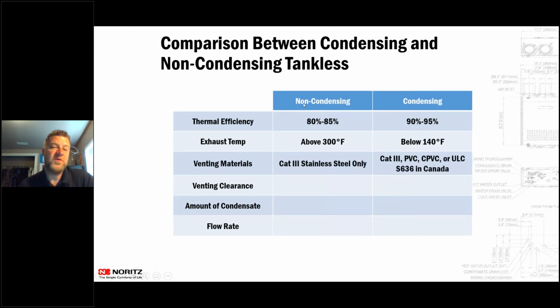So venting materials with non-condensing units, you had to use Cat 3 stainless steel, either 3, 4, or 5-inch stainless steel. With condensing units, you could still use that stainless steel. You could use PVC, CPVC, the ULC polypropylene, or in Canada, that S636, which is like a polypropylene piping.